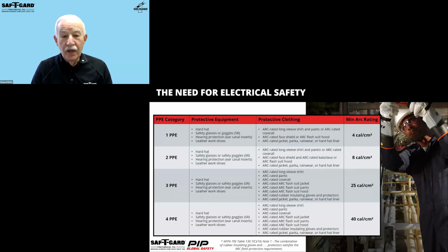NFPA, along with OSHA, mandates and enforces safer electrical work practices under the NFPA 70E standard. Numerous experts and training programs are available to provide guidance on how to keep workers safe and compliant in terms of conducting a proper arc flash hazard analysis. That's step one. Analyze the facility, conduct the arc flash hazard analysis, and then you can determine the PPE category and protective equipment and clothing that are necessary.